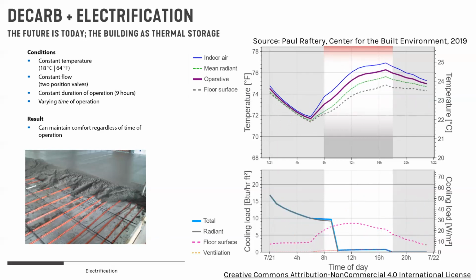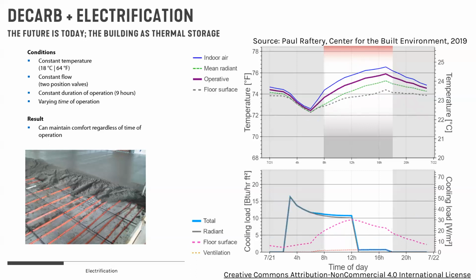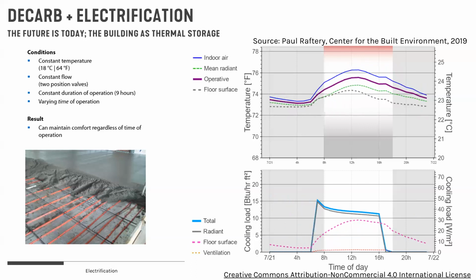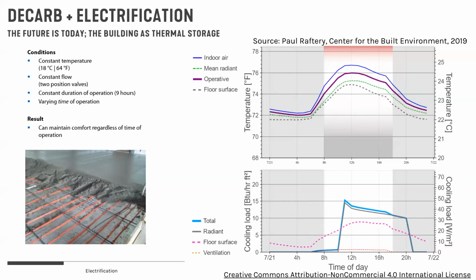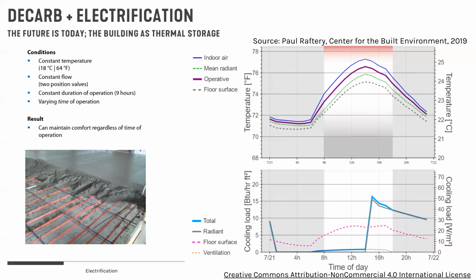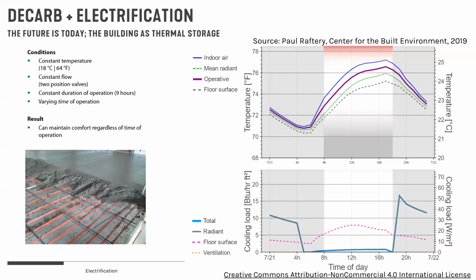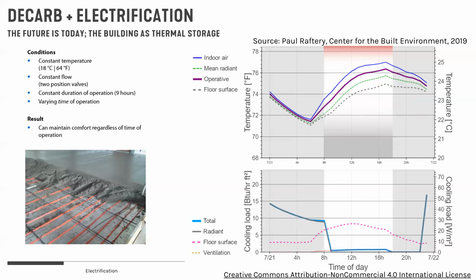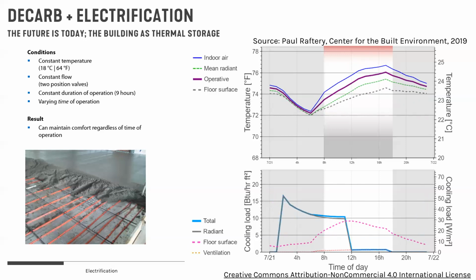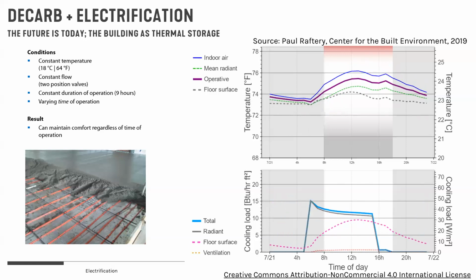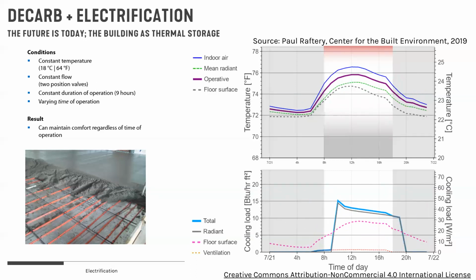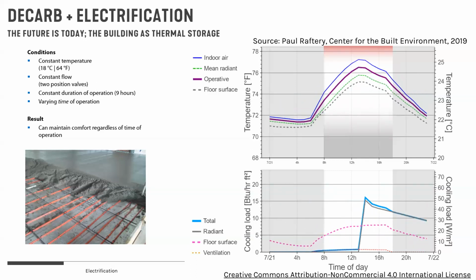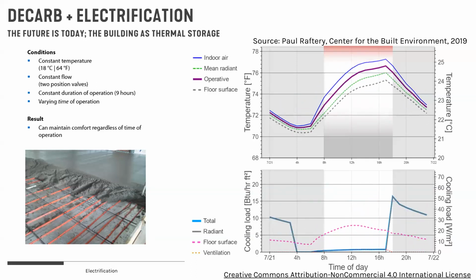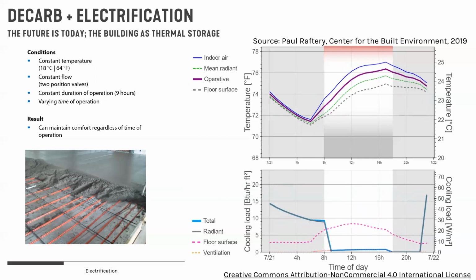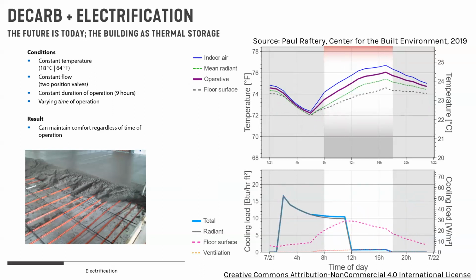A question from Michelle: can we see this in all climates? Mass radiant heating and cooling paired with a good envelope works in nearly every climate, because you can deal with humidity on the ventilation side. So assuming you have a good envelope, yes, you should be able to do this. We're doing it in some pretty extreme climate zones. The downside is if you have a building with a really bad envelope.